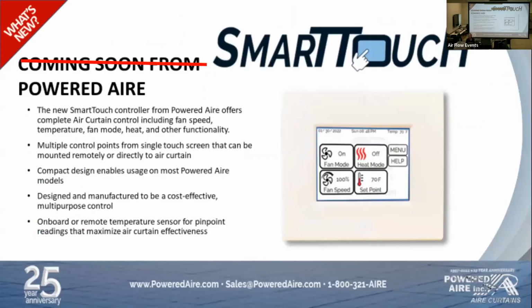Smart Touch. This is something new that we recently introduced. What this does is it's just a touchpad that can pretty much give you any function. The thing that I really like about this is a lot of people want to use the air curtain as a space heater as well as an air curtain. With this, if it's an electrically heated unit, you can easily switch that back and forth. So in a space heater function, it would run off of the thermostat and also the door switch. Let's say the temperature in the space drops below the set point, that air curtain will kick on low speed. And if the door should open during that time period, it will crank on to high speed.